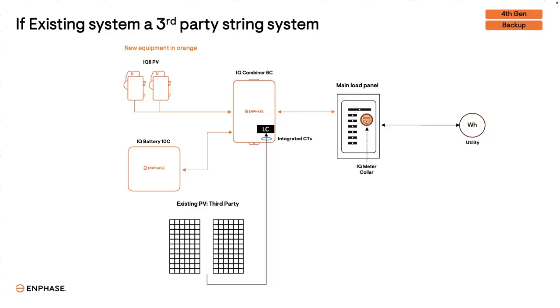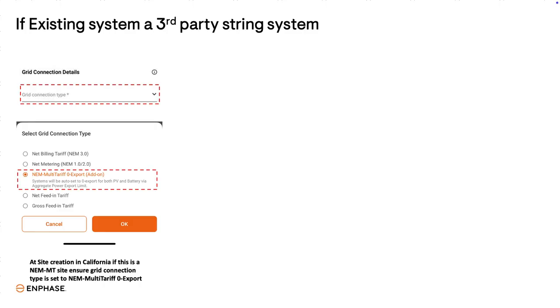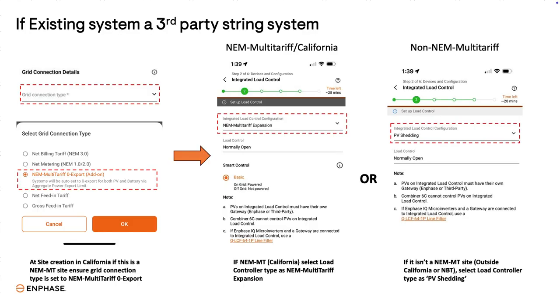If the existing system is a third-party string inverter system, you'll follow these steps. You must create a new site. If the site is in California and it has NEM 1 or NEM 2 status, select NEM multi-tariff zero export for the grid connection type. If the existing system is on the net billing tariff, aka NEM 3.0, select that option. If the site is outside California, select the applicable grid connection type. Then you'll be prompted to select an option for integrated load control configuration. If it's a NEM multi-tariff system, select NEM multi-tariff expansion. If it is a net billing tariff system or a site outside California, select PV shedding.